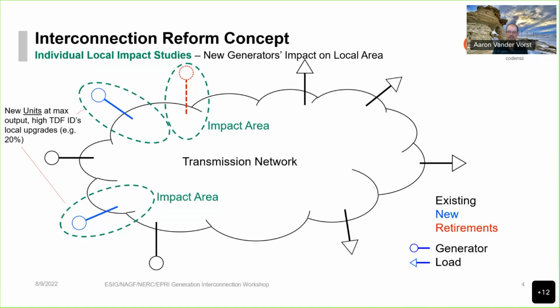The second characteristic is using a high transfer distribution factor, or TDF, to identify upgrades. A high TDF or similar criteria for impacts to voltage, short circuit current, etc. ensures that the interconnection request is only assigned upgrades near the project that it significantly impacts. These mitigations would reasonably be expected to have a high degree of impact on how often the generator is able to inject power.